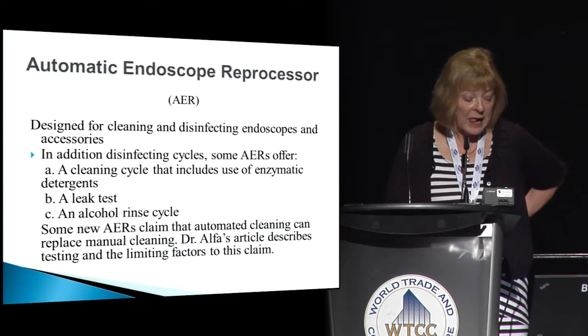systems, and they're not using the cleaning cycle. They're not relying on the AER cleaning cycle, so they still are maintaining their two previous cleaning processes prior to the endoscope going into the AER. Some new AERs have a leak test, and some of them also offer the alcohol rinse cycle.